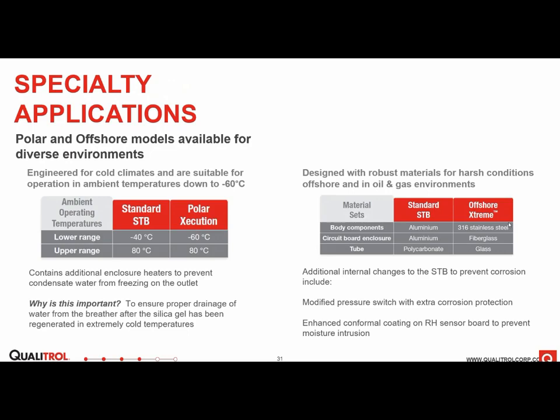Some specialty applications that we can do with the breather are polar extreme, where we can go down to -60C. In this application, we'll add a heater to the outlet port to make sure none of that regenerated moisture being driven out of the silica freezes on its way out of the breather, because that would clog the outlet port, obviously. And then we also have an offshore extreme, which is a breather fully made out of 316 stainless steel. We'll make the circuit board enclosure out of fiberglass, and the tube is obviously glass.